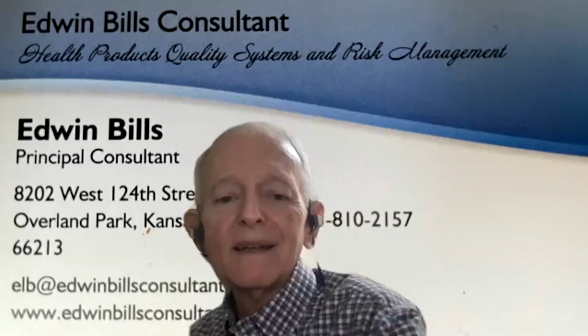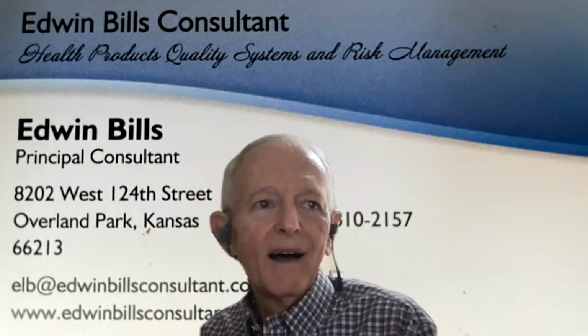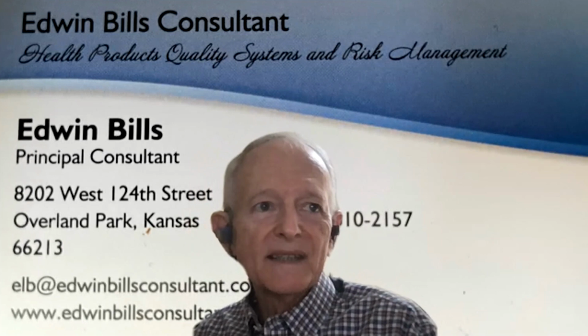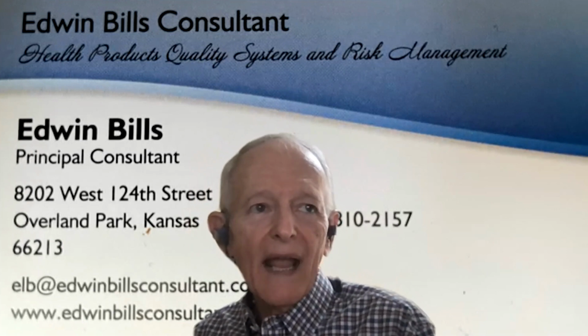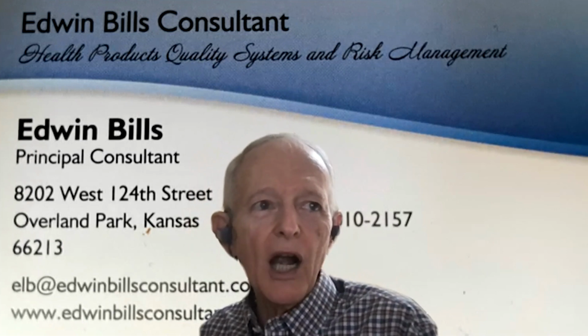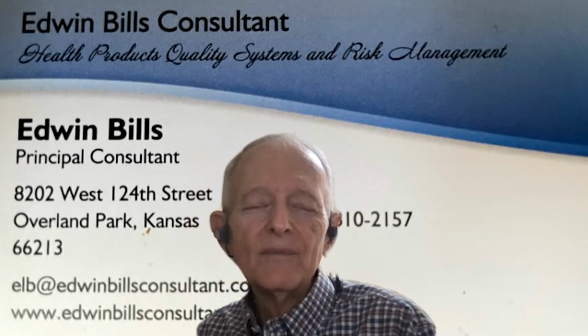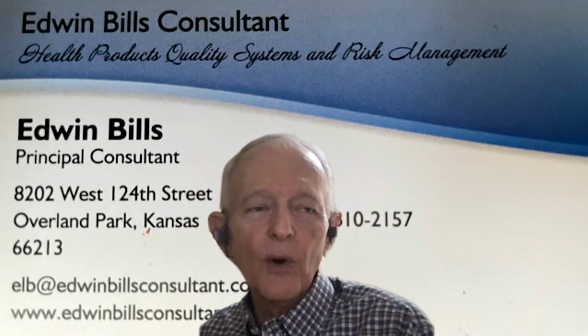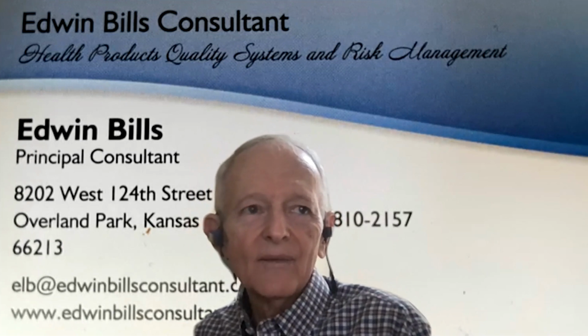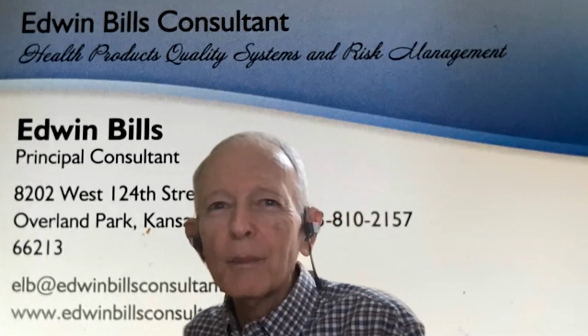I did want to point out, Naveen, we've got a couple of combination products people in here. In the US, there is a technical report, an AAMI technical report, TIR 105, which addresses risk management for combination products. And I realize that some of you are European, but it's still a nice reference, even though you've got a different way to go in Europe than we do in the US. Thank you for bringing that up, Ed.